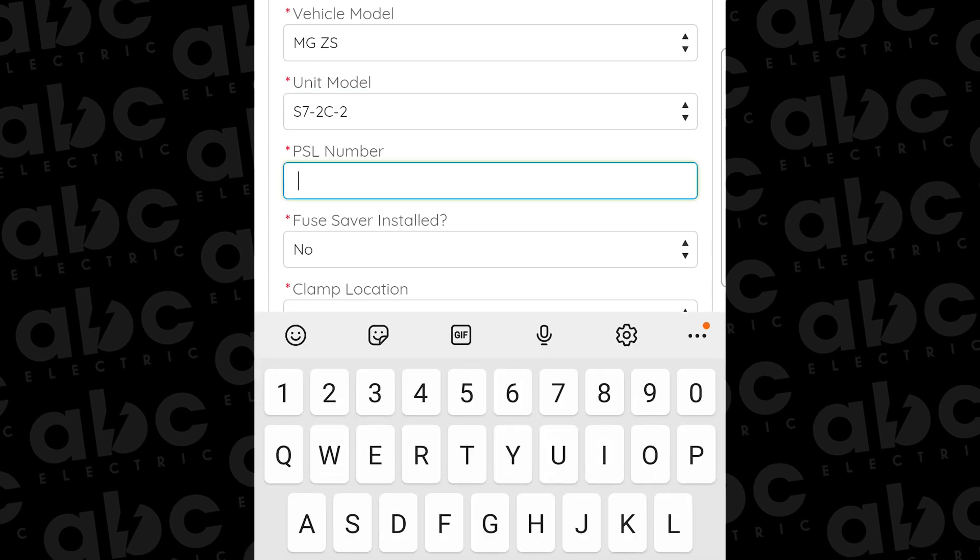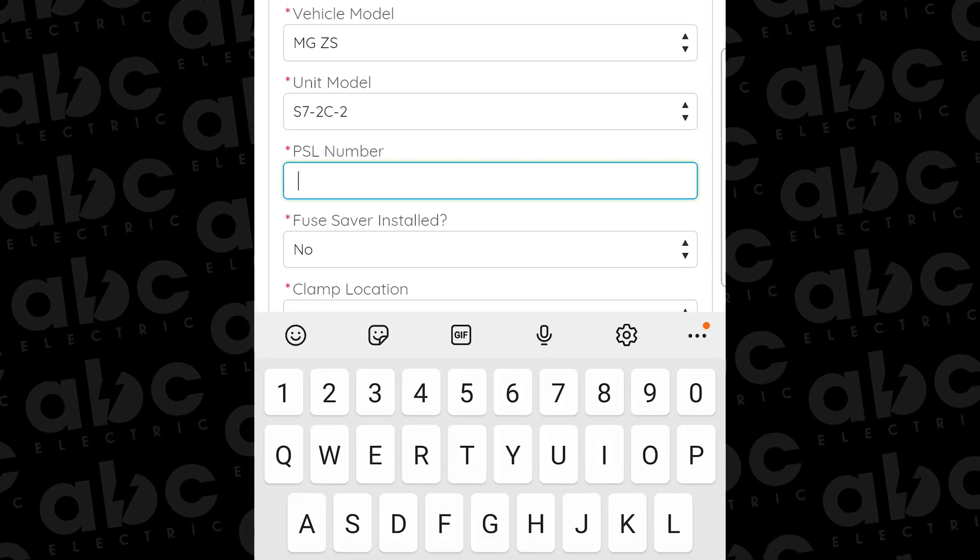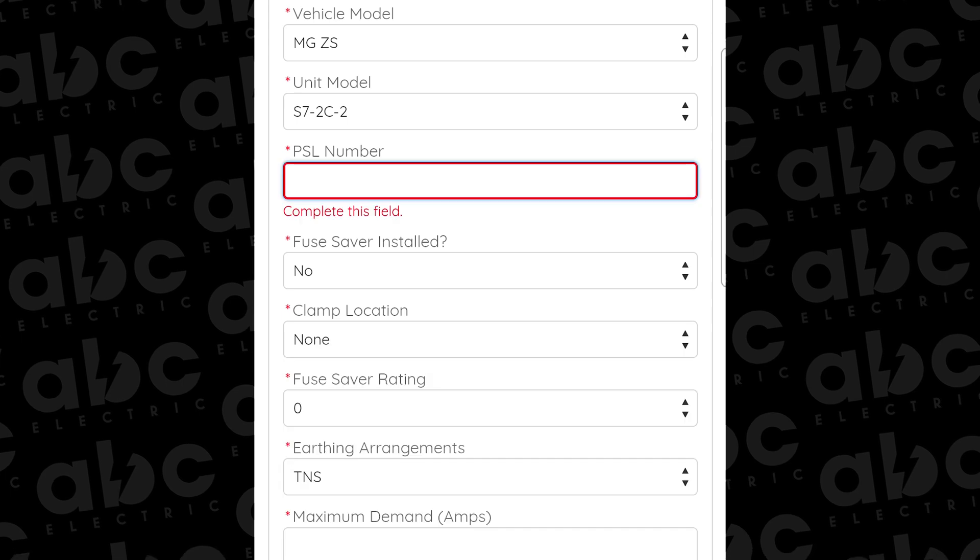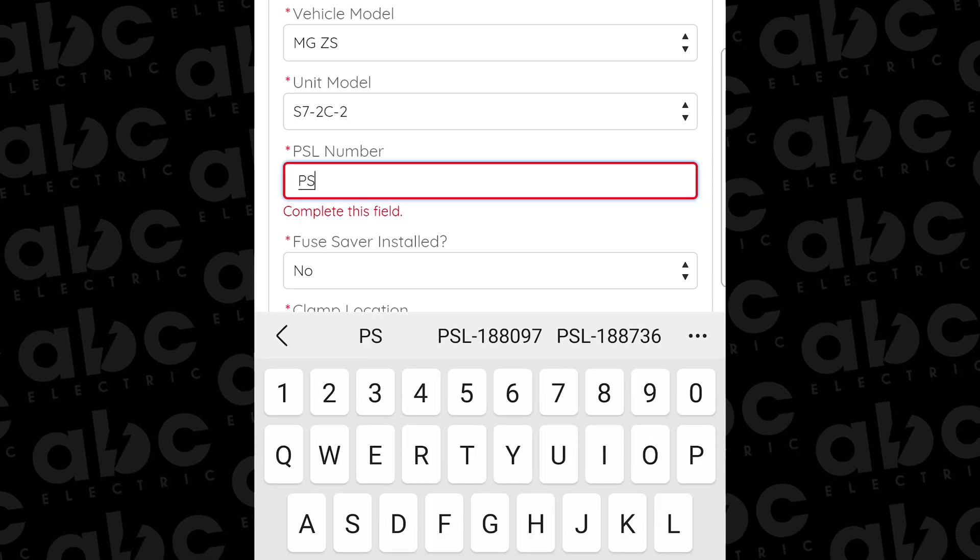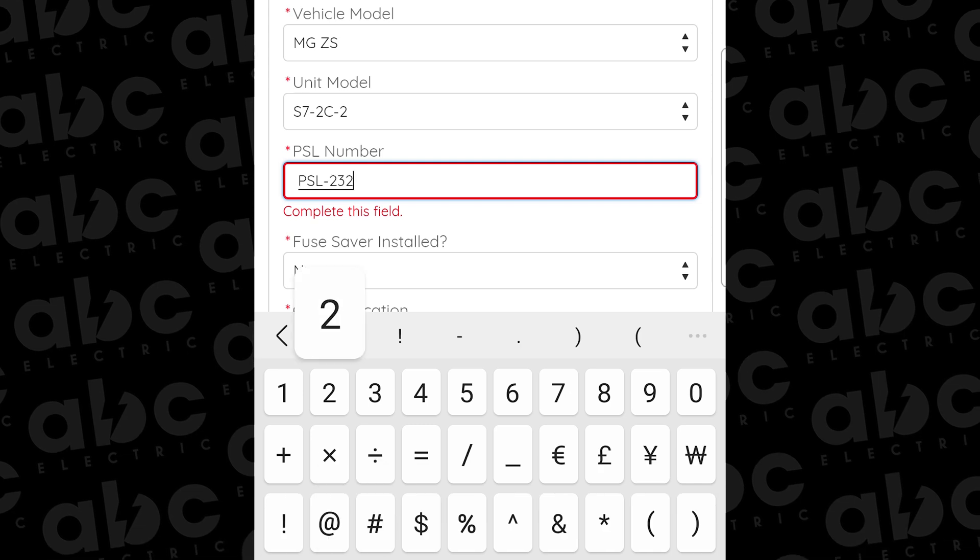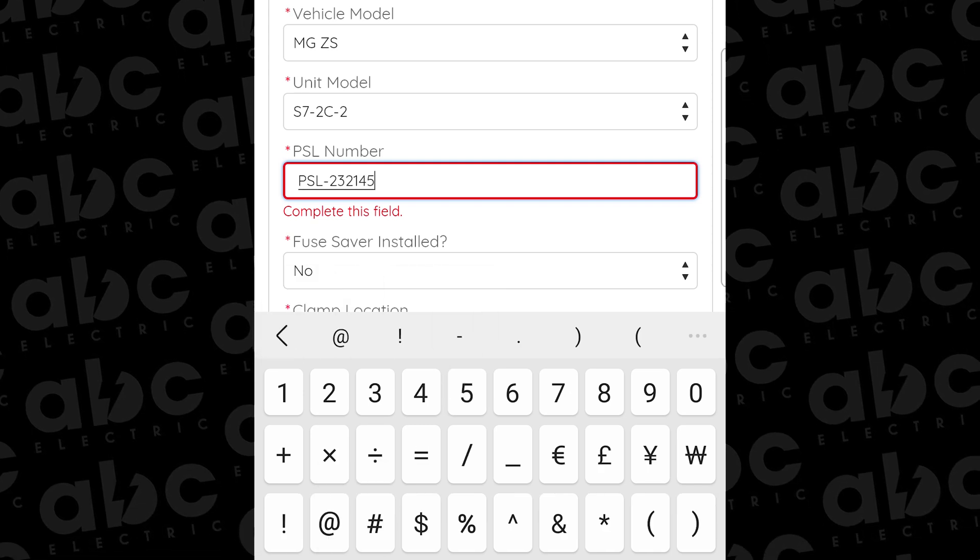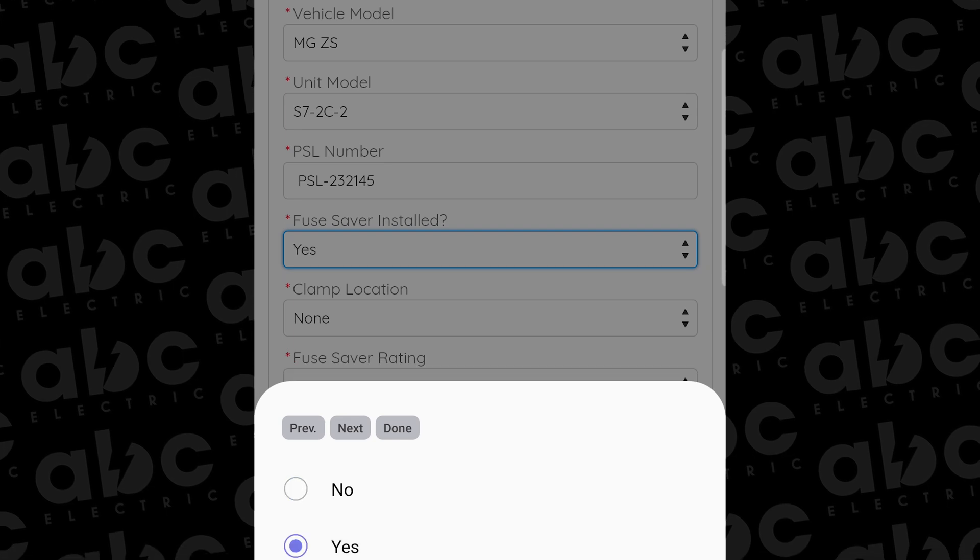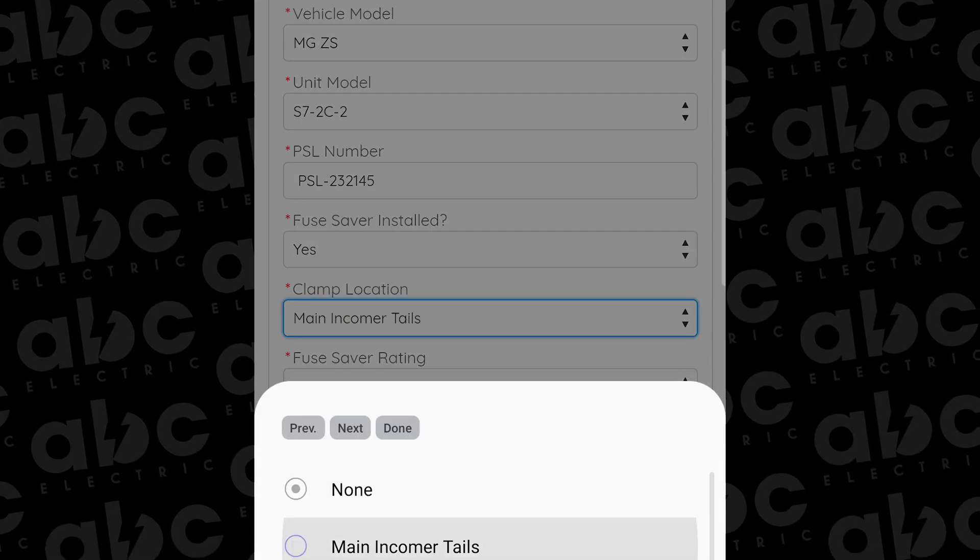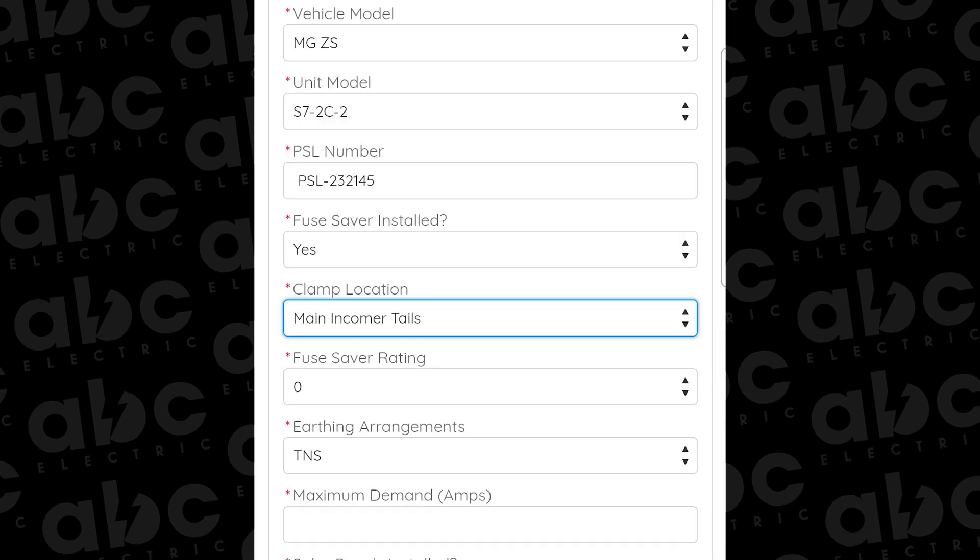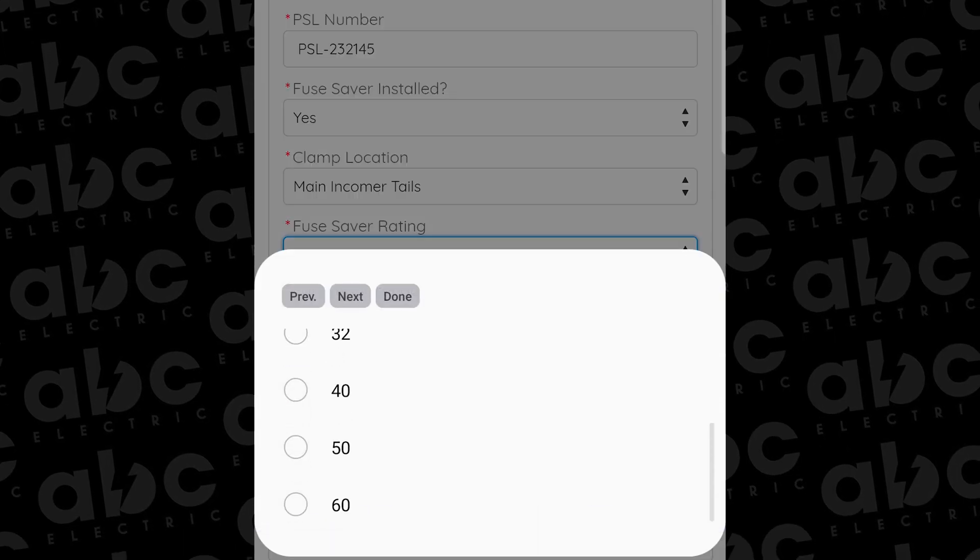Then you're going to enter the unit model. Then you enter the PSL number, which is the Podpoint serial number. You have to enter the PSL in capital letters with the hyphen in between. You can't just enter the number, so that's something to bear in mind. Then you put the fuse saver rating that is set to. So if you set the dip switch on the fuse saver to one, you'll be putting 60 amps in there. Otherwise you do need to make a phone call to Podpoint and it's done over the air.